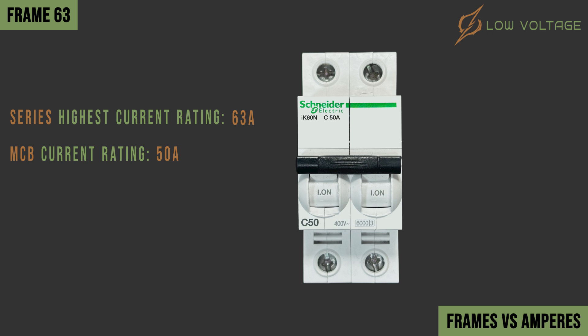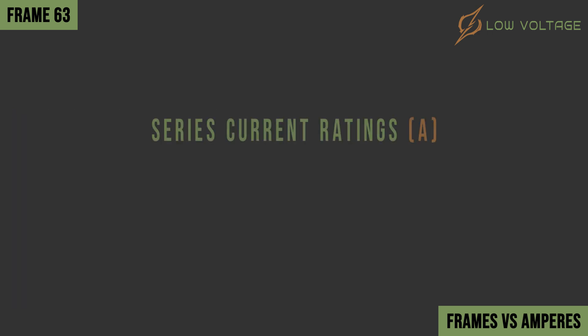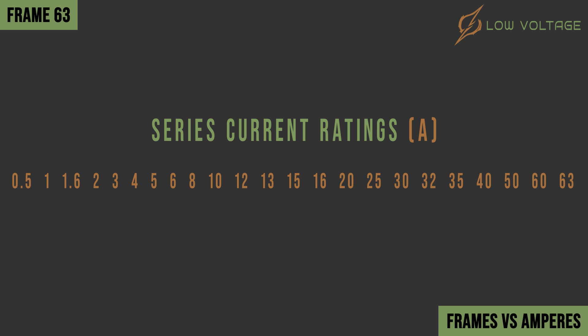The current rating of this breaker is 50 amperes. Printed series codes are considered trade names and are used to identify the type of breaker series and highest current ratings. If we want to know the type and maximum rating, we simply need to check the Manufacturer Product Catalog or MCB technical datasheet. According to the technical sheet, this MCB series has a maximum current rating of 63 amperes, and the current rating of this MCB is 50 amperes. In general, Frame 63 has a current rating between 0.5 ampere reaching a maximum rating of 63 amperes. Each manufacturer has their own current rating series, so values may vary.